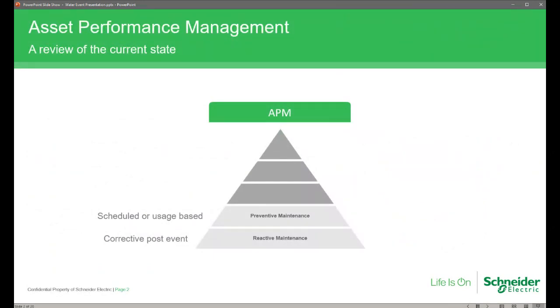The bottom two layers of the APM stack are the reactive and preventative maintenance levels. Reactive would see a corrective action carried out on an asset based on a critical event like a failure. A typical example is an alarm in a SCADA system indicating a failure, and a member of the maintenance workforce is dispatched to resolve the fault. The next level is preventative — routine-based maintenance based on time or usage statistics, such as run hours or number of starts, and when exceeded it triggers a maintenance work order request.